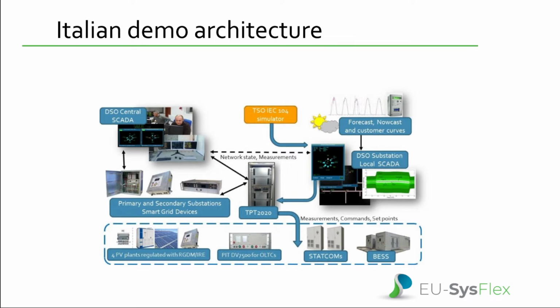We emulated the exchange of information between the local SCADA and the TSO SCADA, and in this part of the chain, the simulated TSO can receive the capability range from the local SCADA, can choose a specific set point of reactive power included into this capability range, and send it to the local SCADA.